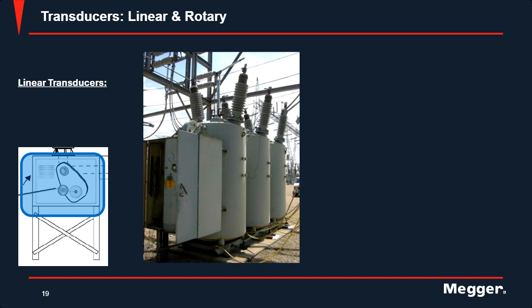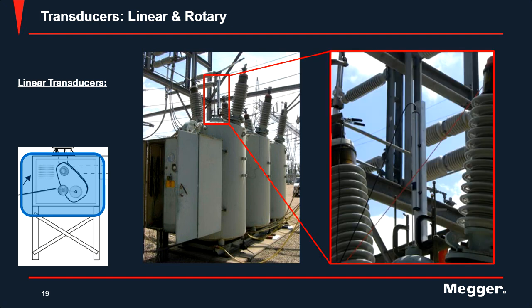So they're all two different types. As I said, there's a linear and rotary. So linear, I got a little picture here on my bulk oil circuit breaker. It's directly in line with the operating mechanism. Obviously, the type used depends on your circuit breaker. Most of the breakers allow for either one to be used. However, do follow the manufacturer's recommendations. But once you select a certain type, you should stick with that for any subsequent testing that you do. That way you can trend your data over time. So if you use a linear and then you go out and use a rotary next time, those two values, you can see some comparisons, but they're not apples to apples. It's more apples to oranges.